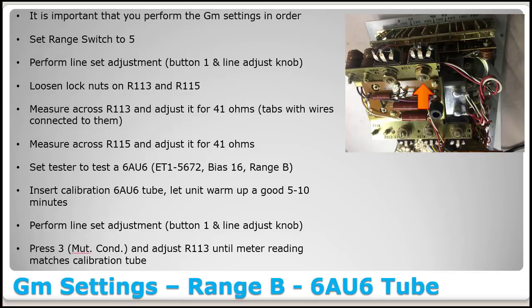And you may wonder, well, which of the 3 leads do I connect to? Well, only 2 of them have wires on them, so hook to the 2 that have wires connected to them. First you're going to adjust R113 for about 41 ohms. It doesn't have to be exact. It could be 42, 43, just right in that range. And you're going to want to do the same then for R115 down here. Adjust it and get it for 41 ohms. All that you're doing right here is making sure that you're somewhere within the range of the calibrations for this tube when you start out, so you're not completely off scale.